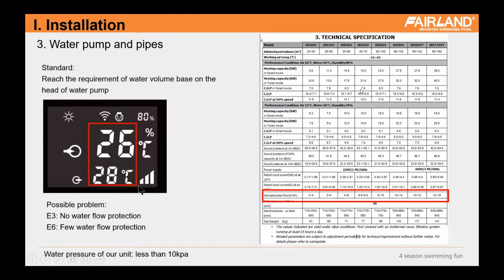And sometimes they choose a small size water pump, so they may not get enough water flow. That will cause a big gap, a big difference between the inlet and outlet water temperature, like more than 10. If it is more than 10 degrees, the unit will display trigger code E6 to give a warning that the water flow volume is not enough.